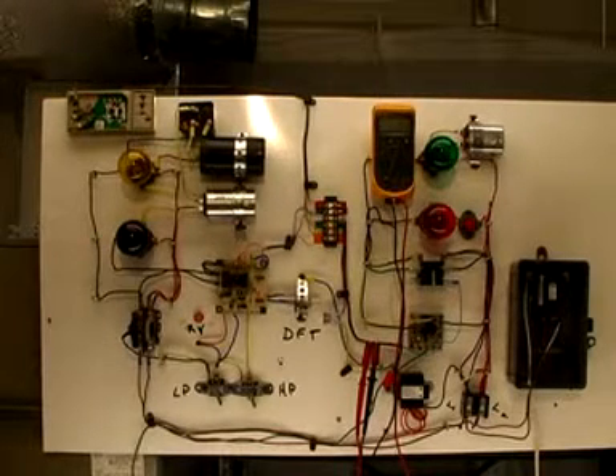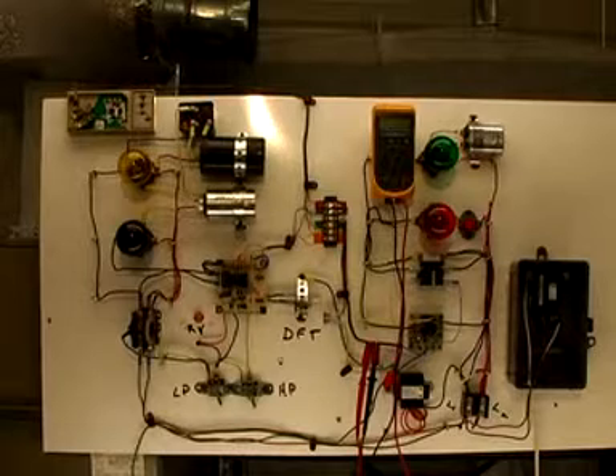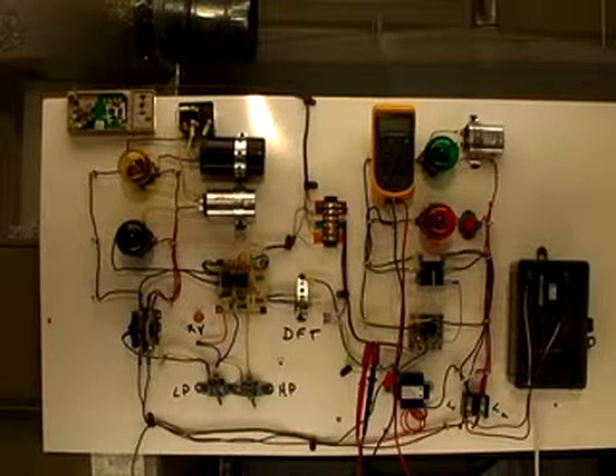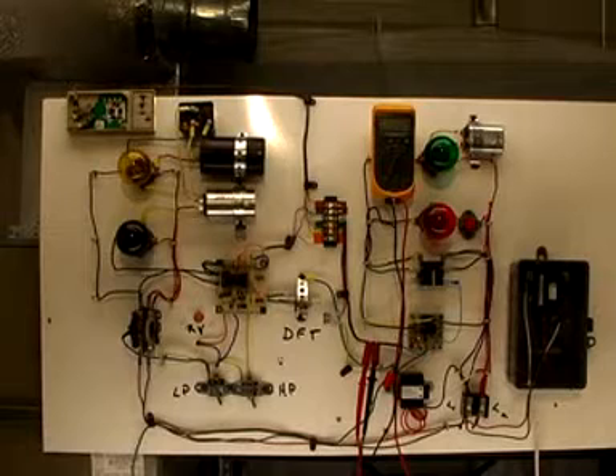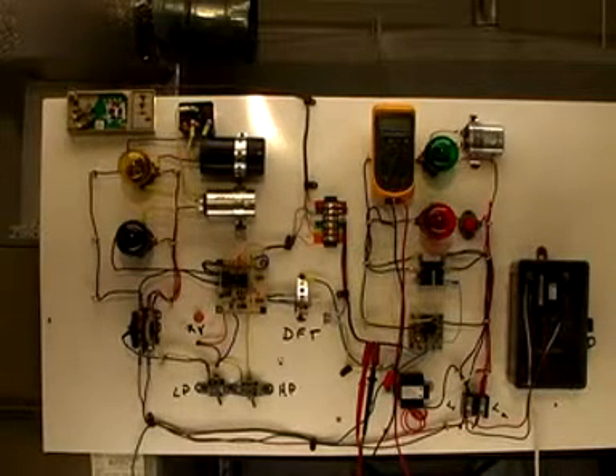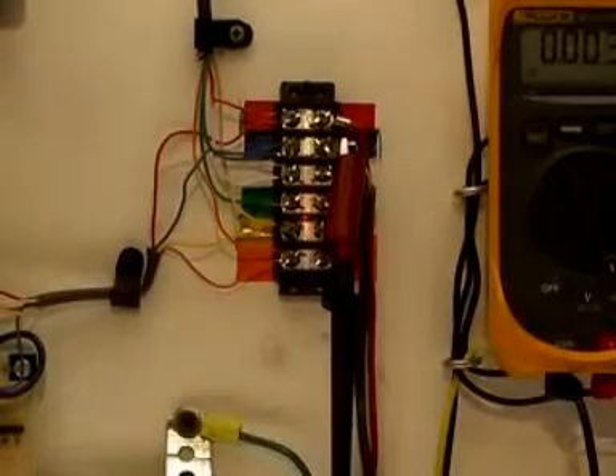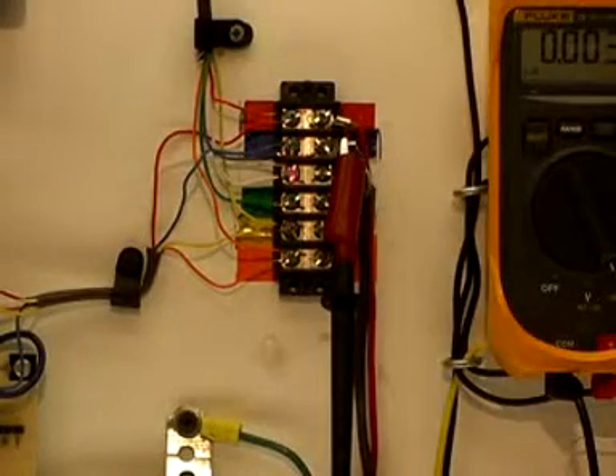Like go to the thermostat and just energize the blower. See if the fuse stays okay. Then you can energize the contactor and see if the fuse blows. Then you can energize the reversing valve circuit by putting the system in cool. And then from the previous time when we knew everything was normal, we've got three possible circuits that have shorts in them. And as I said, there's only one I know that has a short in it.